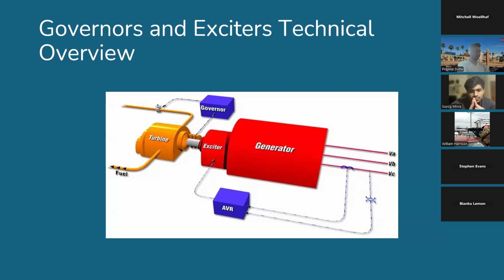Several critical control functions are required for proper operation and are part of the deliverables for a project. Voltage raise and lower controls, handled with the exciter, allow adjustments to the generator's terminal voltage to match system requirements. Similarly, speed raise and lower controls are handled in the governor, and they fine-tune the governor's operating frequency.